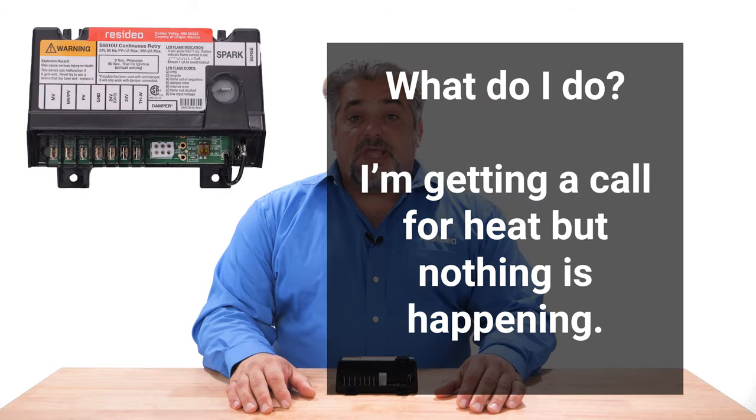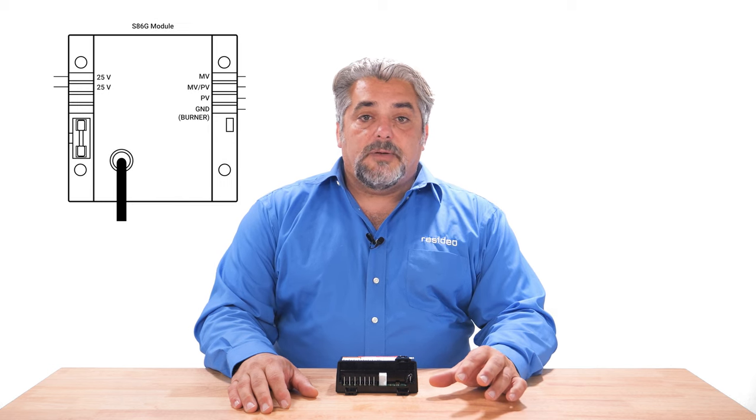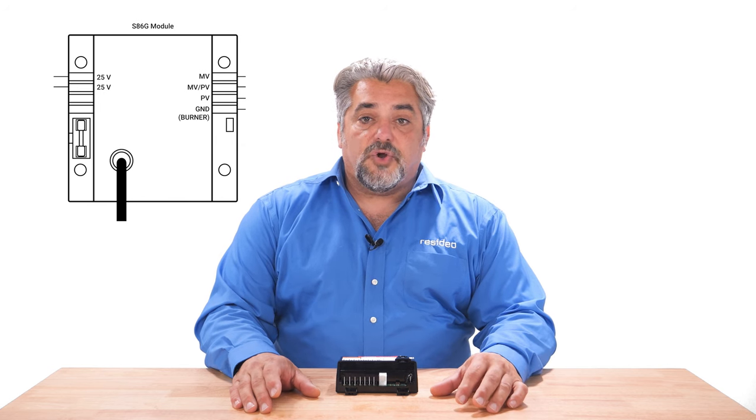A common call we receive for the S8610 is the system calls for heat and nothing is happening. This often occurs when the technician has replaced one of our old vintage intermittent pilot modules. What they experienced was the old module had good power on the 25-volt terminals and the igniter was sparking, but there was absolutely no power getting to the gas valve on the MV/PV or PV terminals.